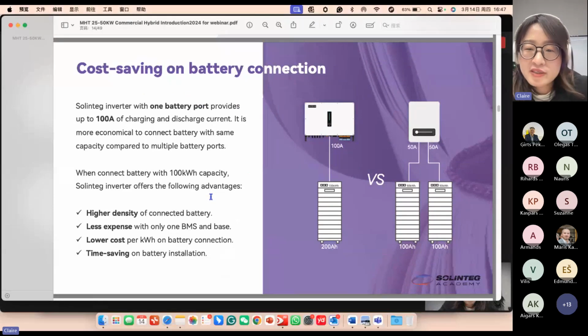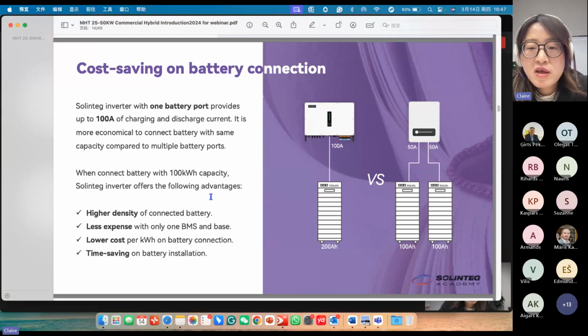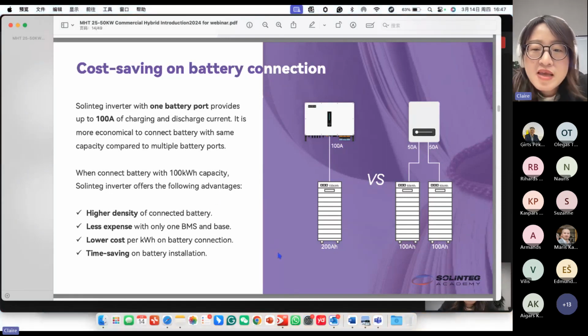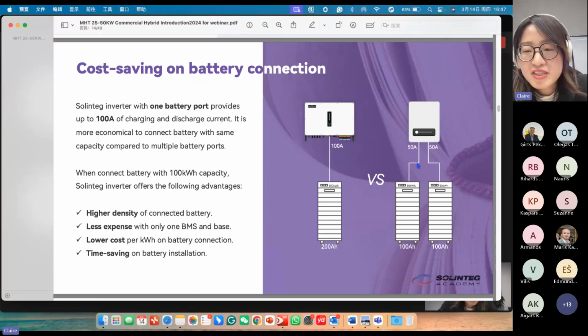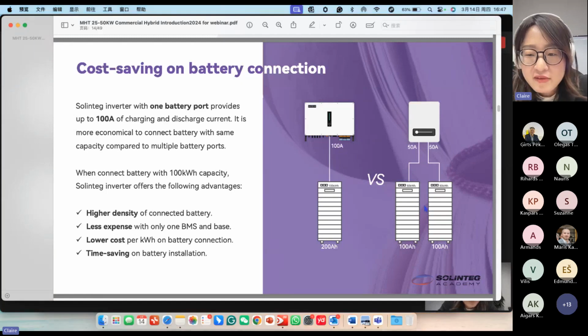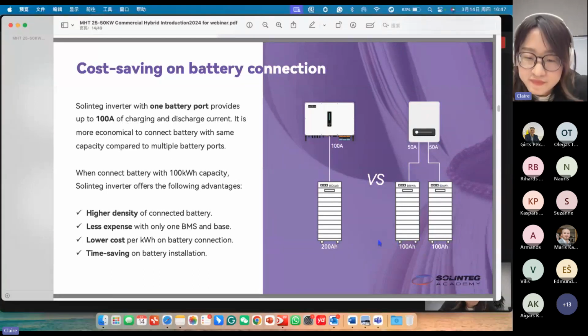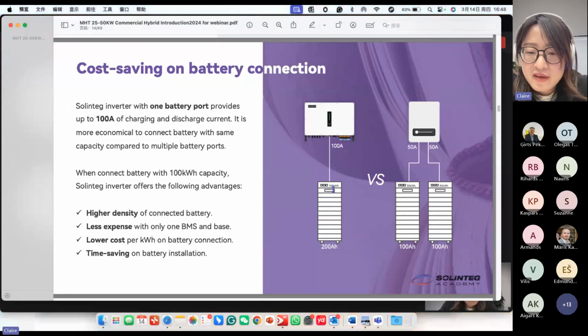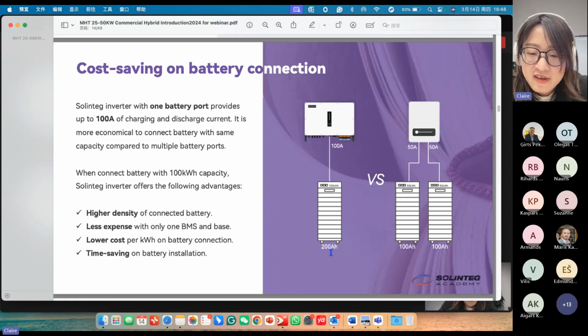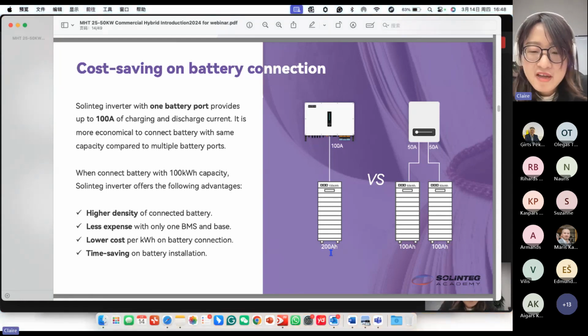And talking about the battery charging and discharging current, we have a battery charging discharging port with a maximum current of 100 amperes. If the customer wants to connect the same capacity battery, another solution may have only 50 amperes charging discharging current. They have to connect two clusters of battery, and we only connect one. You know, for a two-cluster battery, the customer has to buy two BMS, two basements. So this will cost more money, and the battery capacity is smaller than our inverters. You can see this one is 100 ampere hours and this one is 200 ampere hours. So we all know that the bigger the power, the lower the price for each watt.